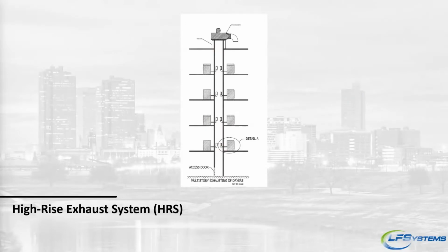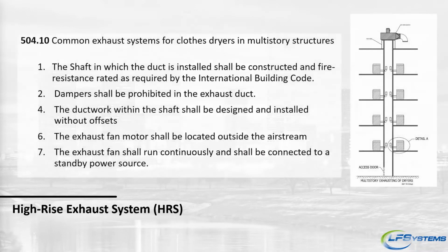Now there's some code things you have to look at. And again, we're going to focus on the dryer codes, but a lot of these will apply to your kitchen and your bath. The shaft and the duct must be installed and constructed in a fire resistant rated manner in accordance with the IBC. Dampers shall be prohibited in dryer exhaust. So I mentioned this in my commercial presentation. You cannot have any impediment between the dryer and the termination. Dampers, fire dampers in that duct become lint collectors. Lint catches on fire and fire is bad. Okay, so we can't have any dampers in the airstream. We'll tell you how to get around that when penetrating that fire rated shaft.